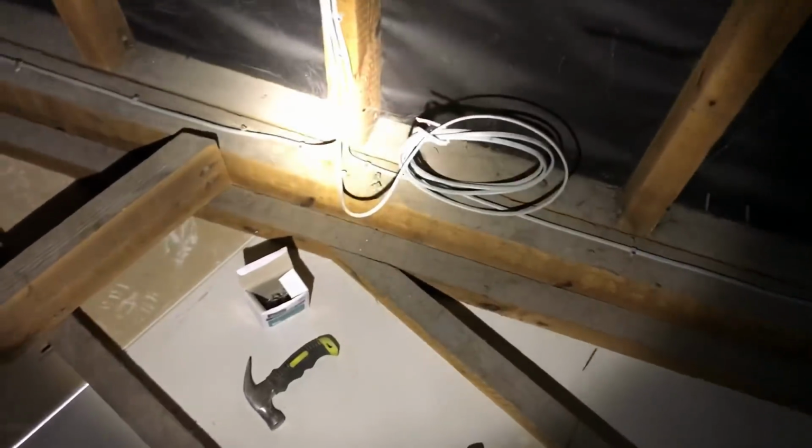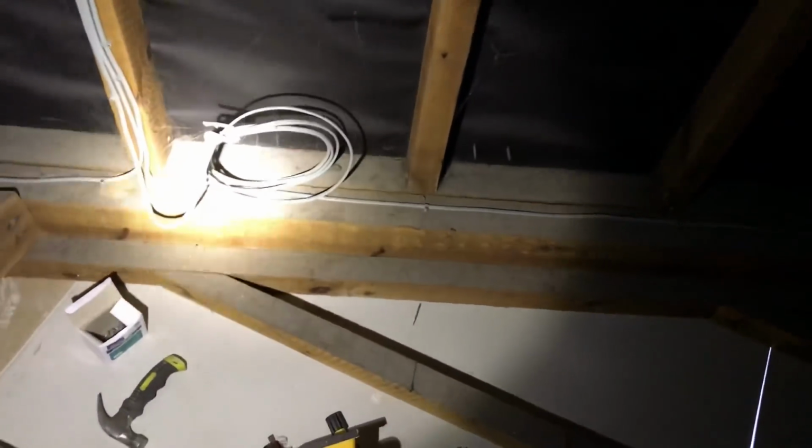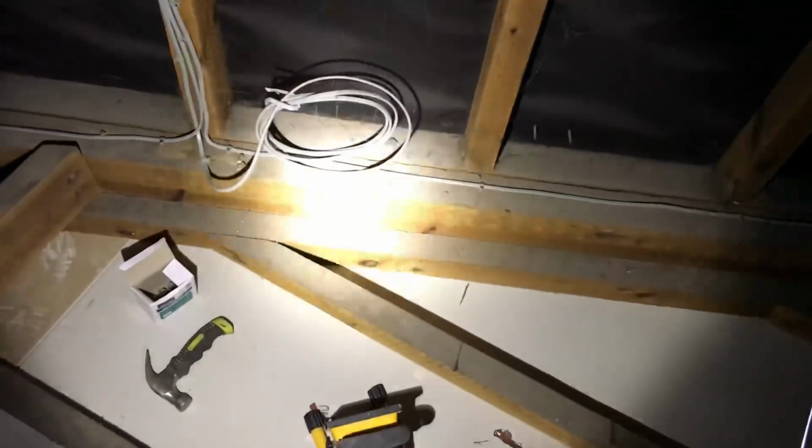At the front of the shop now, where there's going to be a big sign on here. So I've left a looper cable here, because they've got 2 spots that are going in the front of the shop window here. They don't know the position, so we just get the first feed in from the switch. So that'll be a switch line and a neutral, and then we'll get the positions once they know what they want. That's for a light that's going down on that pillar.